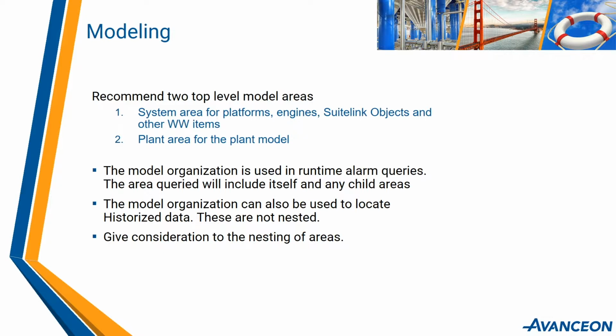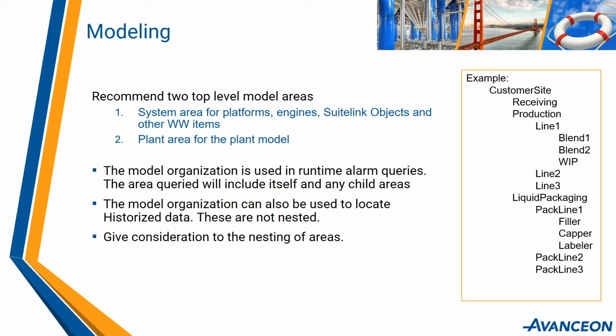The areas queried will include itself and any child areas. The model organization can also be used to locate historized data. These are not nested the same way that runtime alarms are. So give consideration to your nesting and try not to have too many layers because then it just gets confusing.